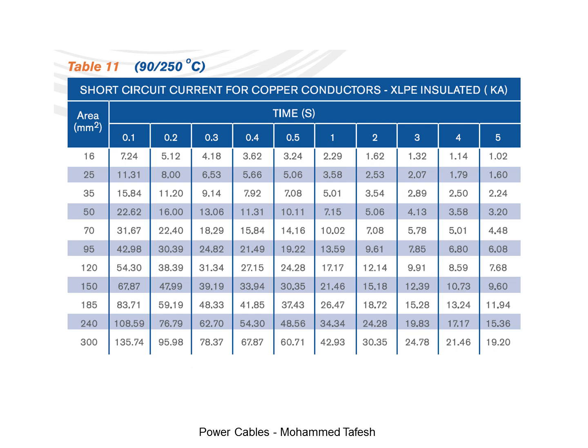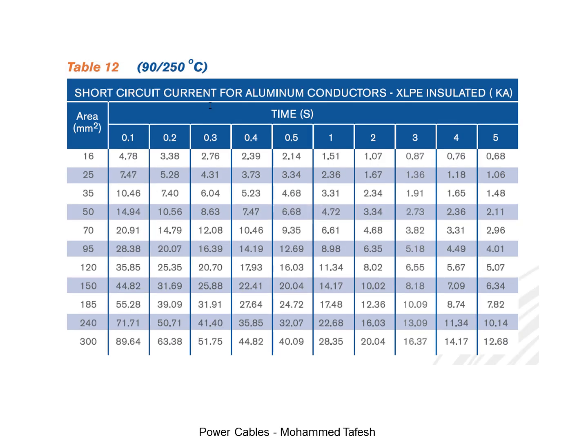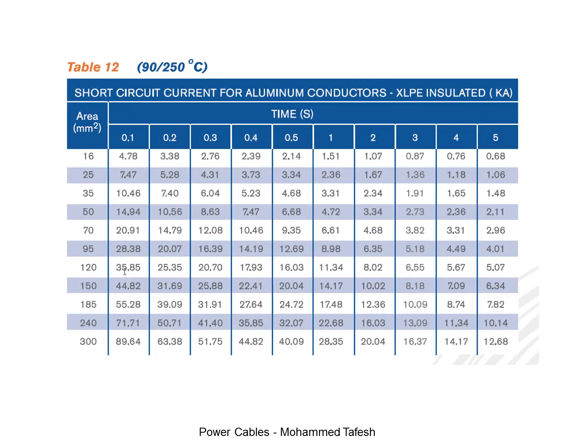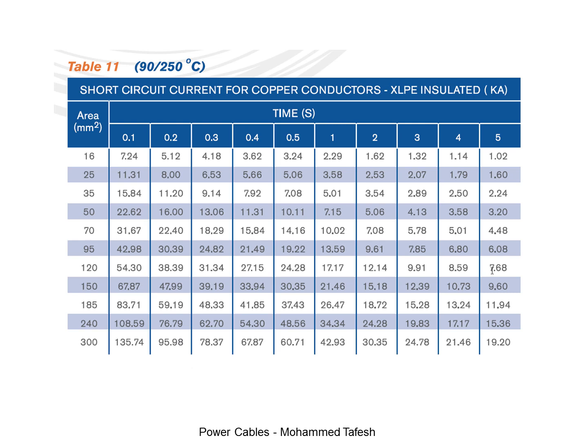In other words, at the beginning of the short circuit the value increases, but after many seconds the value decreases. Looking at aluminum conductors, the value differs from copper conductors. If we choose the same cross section area of 120 mm squared, we note that the value decreases — at 0.1 seconds it is 35 kilo-amperes, and at 5 seconds it is 5 kilo-amperes, while for copper conductors at this cross section area it is 7 kilo-amperes.